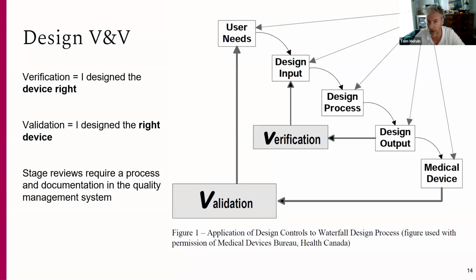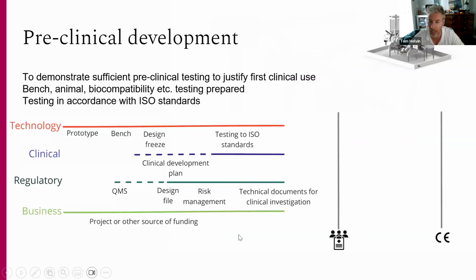So you have to break down all of your components. You have to think of the user needs. You have to map your design inputs and your design outputs, and then you have to verify all of the different outputs and then validate the overall device. So if you have a single device with 100 components, you verify each component, and then you validate that the overall product is designed as intended.